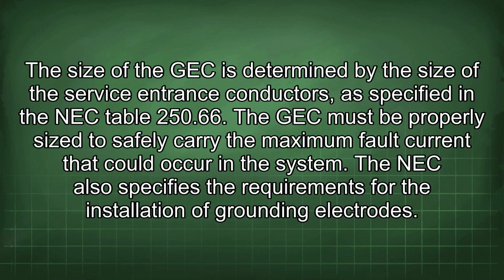The size of the GEC is determined by the size of the service entrance conductors as specified in the NEC Table 250.66. The GEC must be properly sized to safely carry the maximum fault current that could occur in the system.